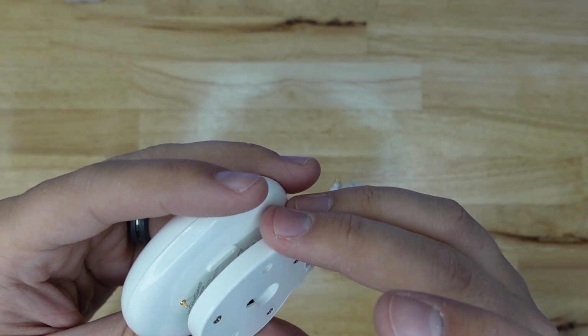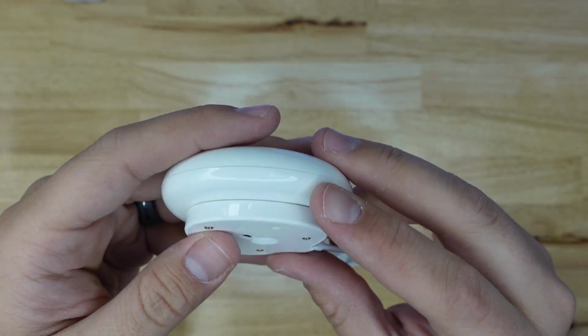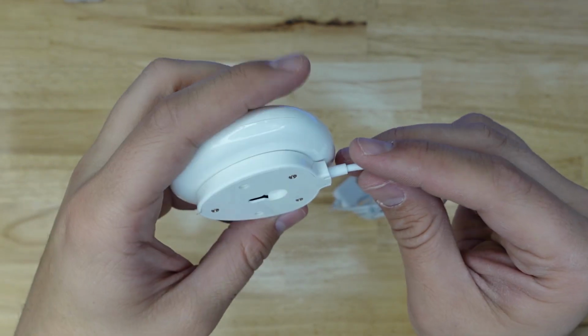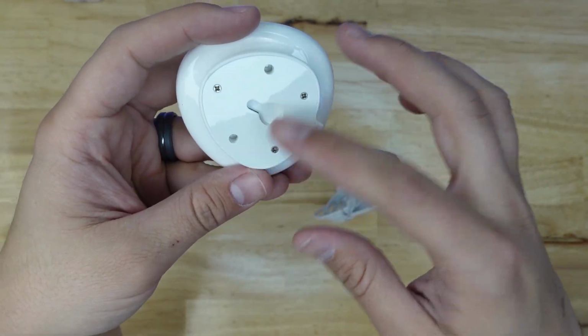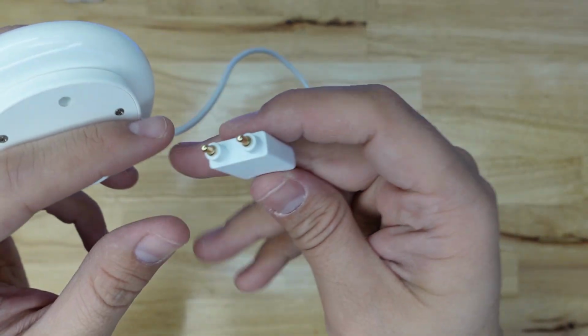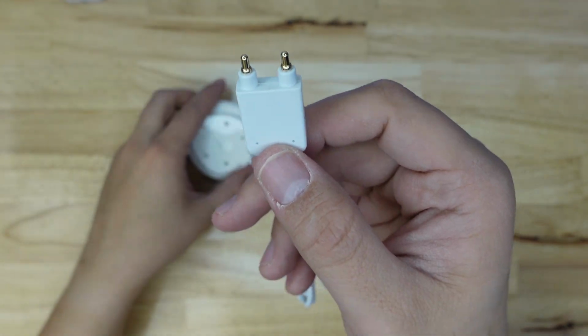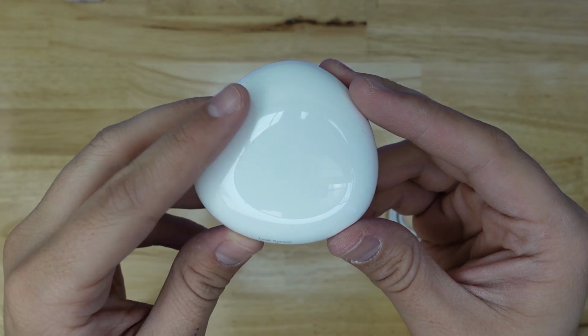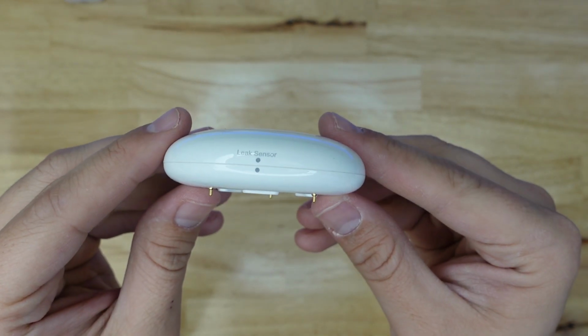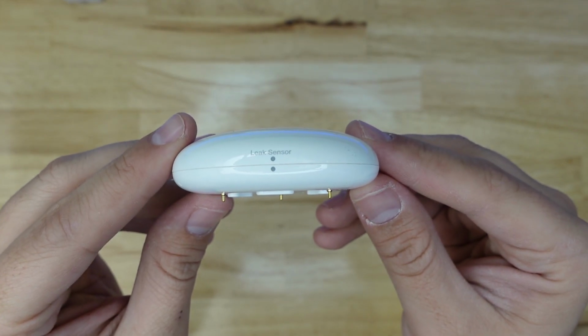When aligned properly, the electrodes make contact with the conductive pads on the magnet end of the probe, and the magnet end of the probe has a slotted hole on it that can allow the sensor body to be mounted to the wall when you're using it. While the underside of the sensor body does have 3 electrodes, only 2 of them actually sense water. The other one's really just a foot for supporting the device.